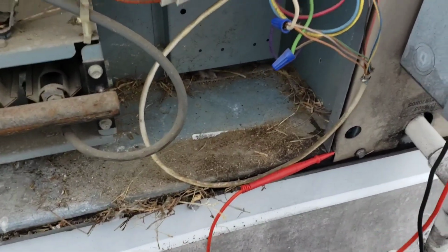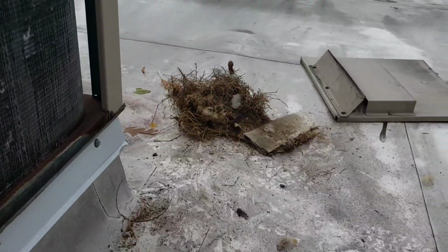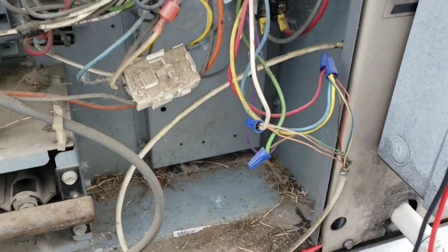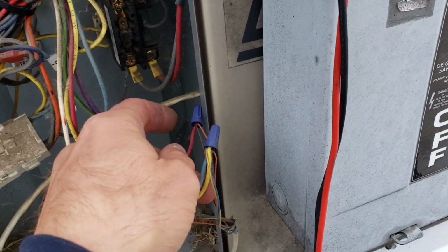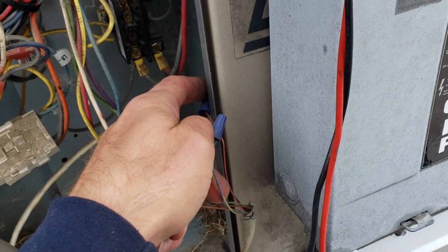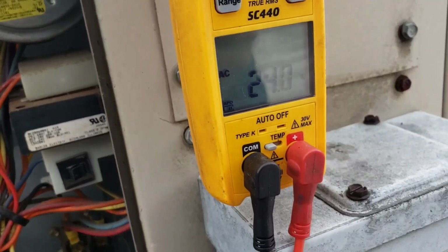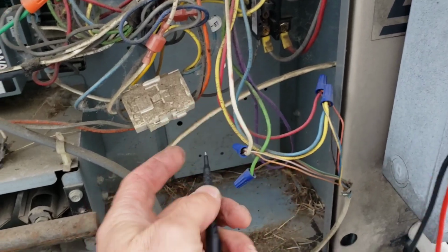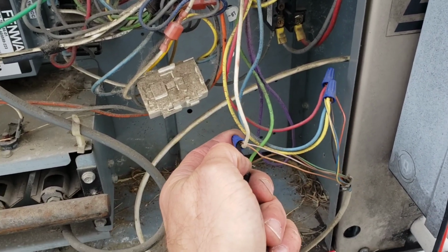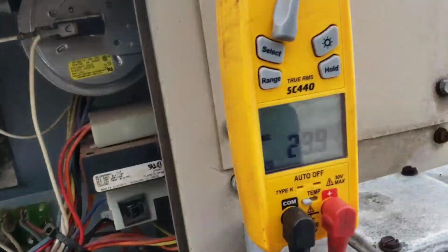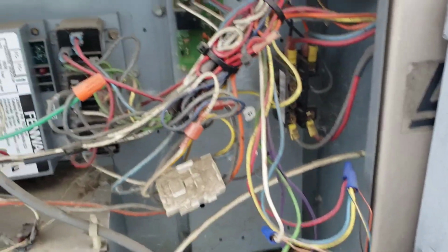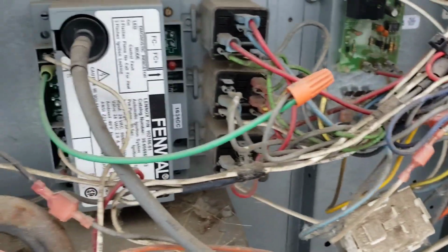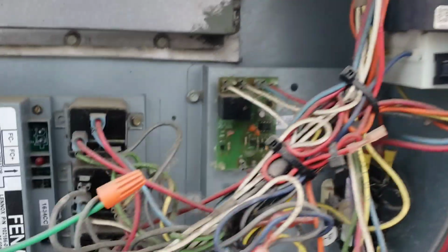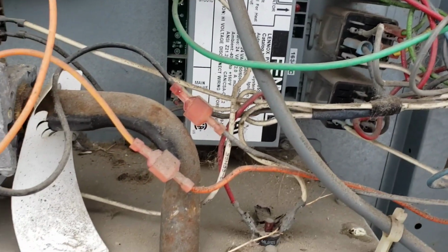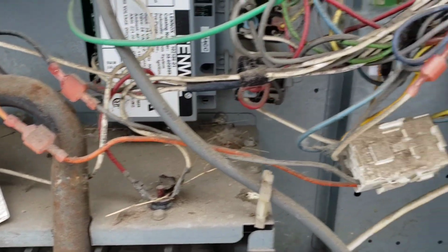Alright, step one, remove giant bird nest. Check. Step two, check for 24 volts. Check. Step three, check for 24 volts on our call for what I assume is heat. Check. Step four, check for lights - that'll give you the answer of what's wrong with it every single time. And we have no lights. Well, shit.